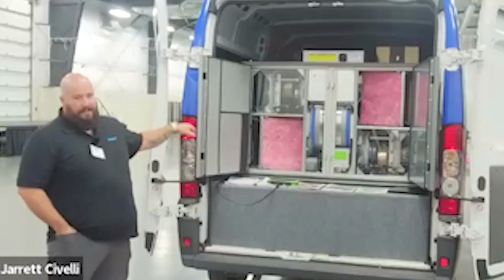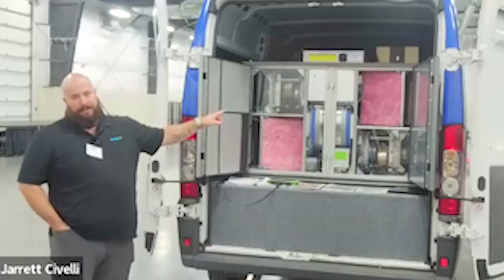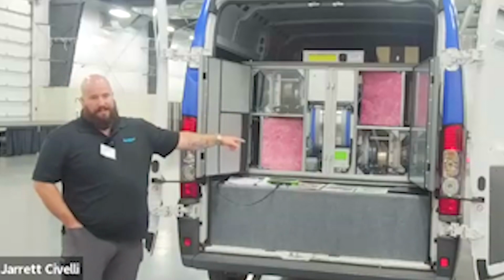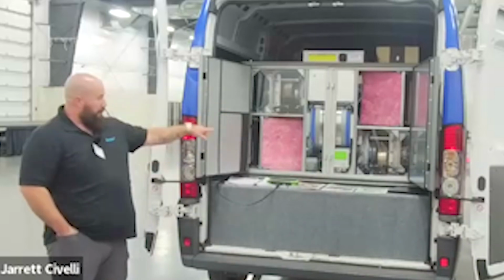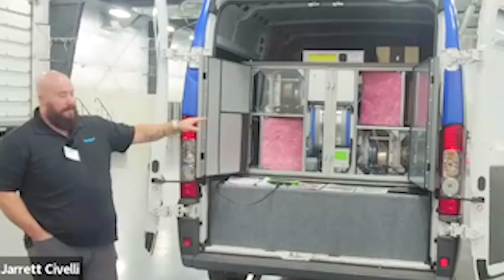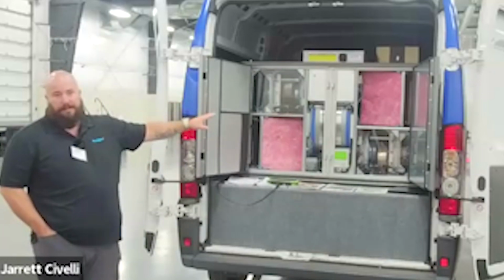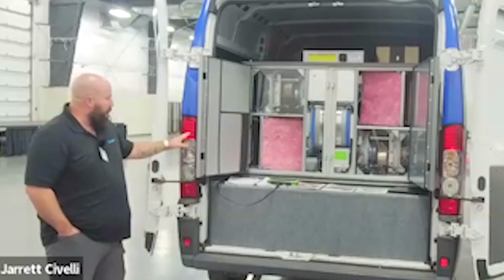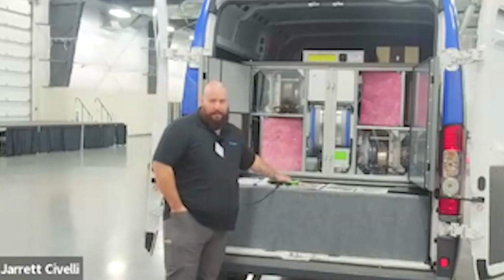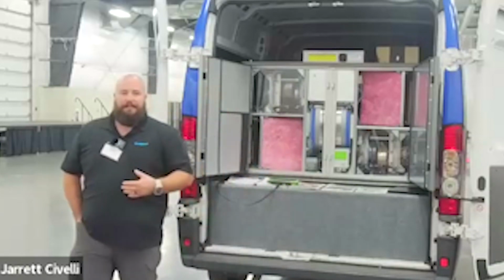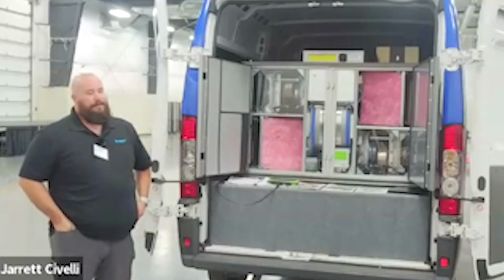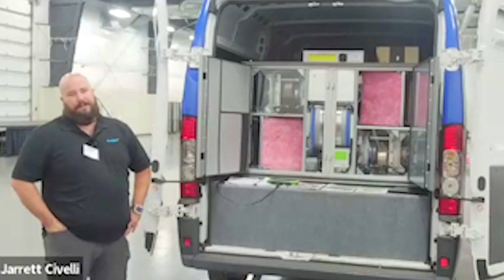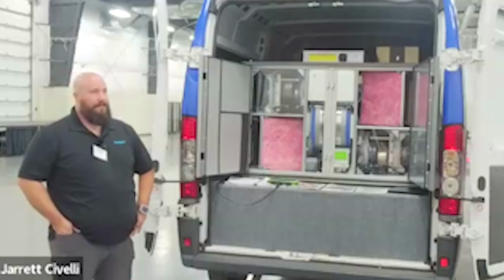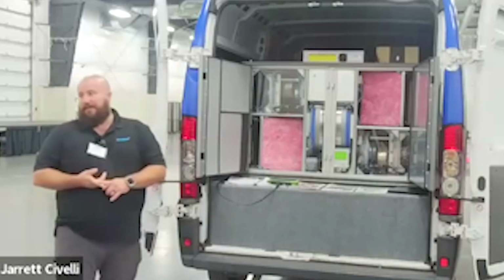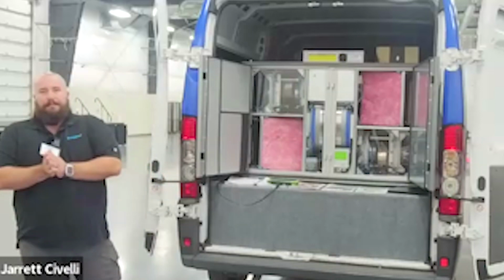So we see the incoming air temperature, we see the pressure across the wheel, we know the fan speed, we know the pressure and airflow for the fan, supply and extract. All of those things come back to this controller that the technician can look at and make adjustments. There's a whole host of control points that you can set to set the unit up the way you want for balancing or energy efficiency for your control strategy.